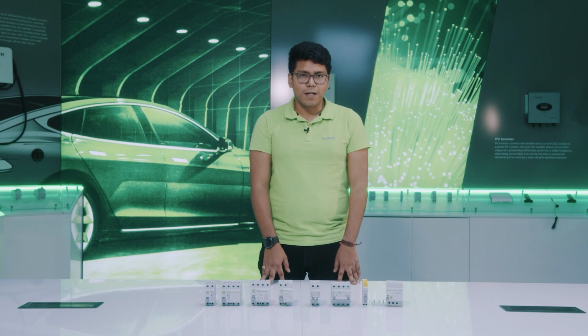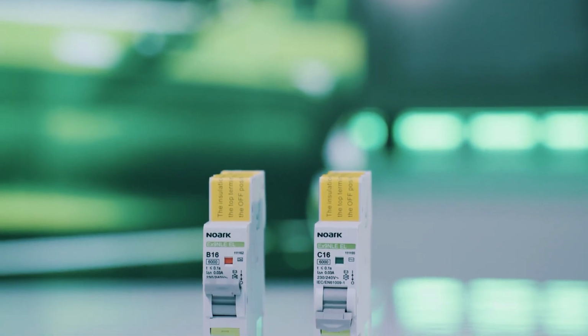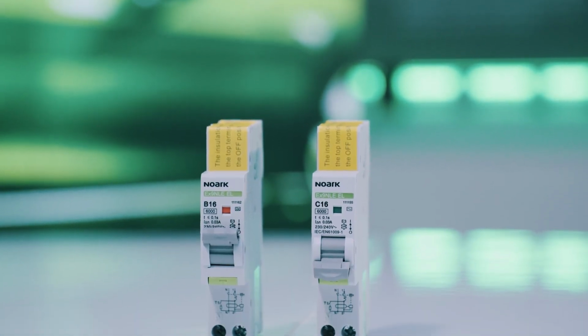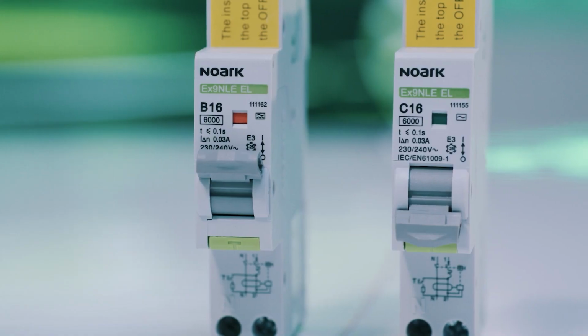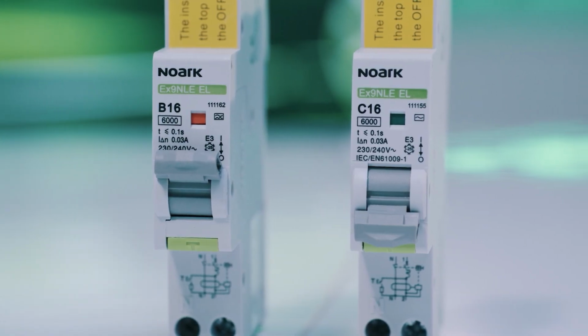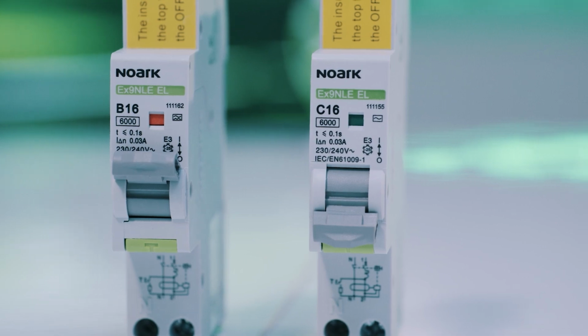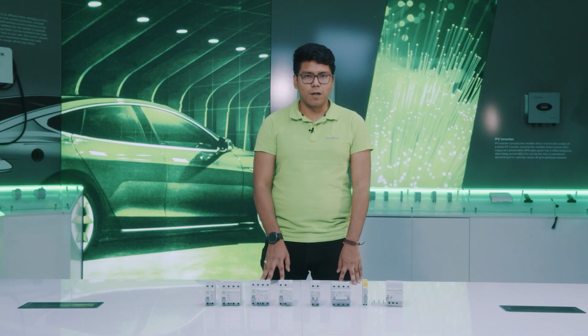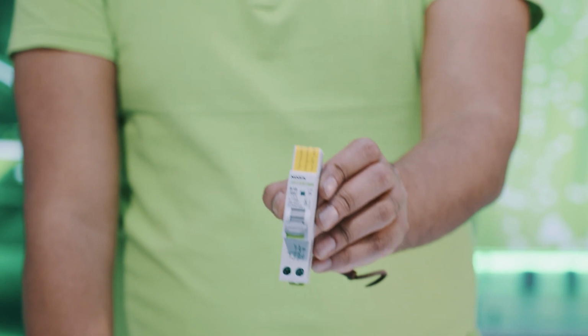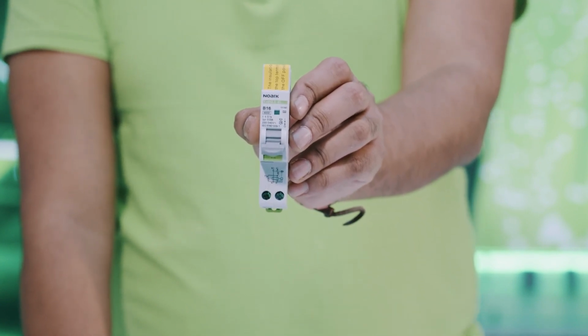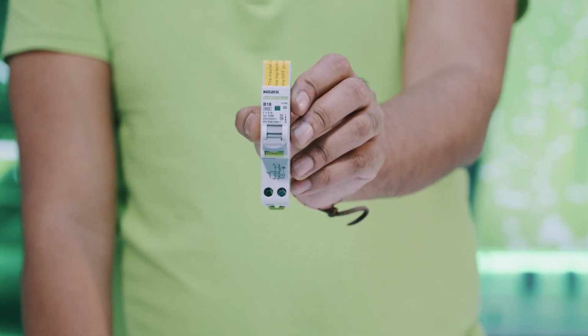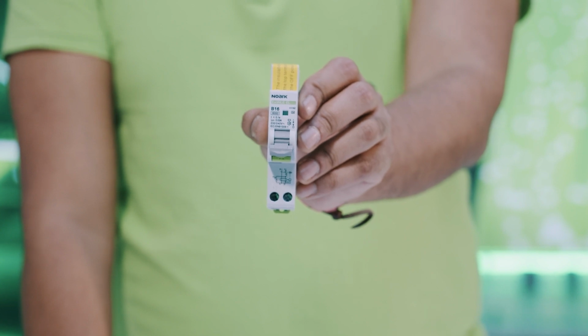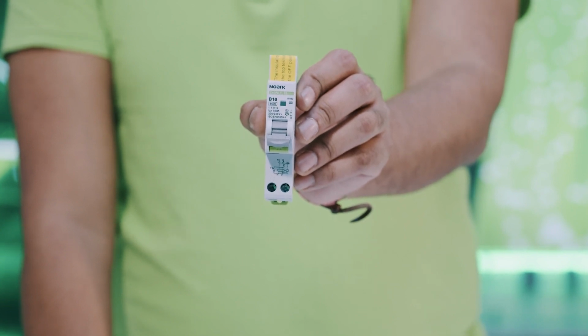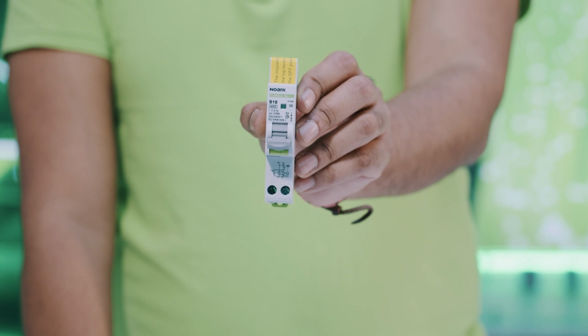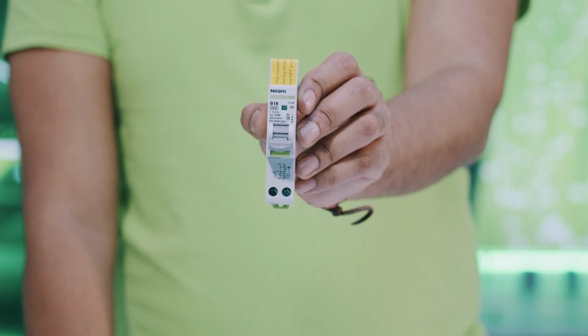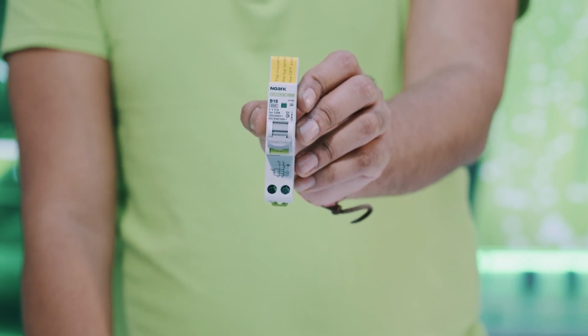Another type is the EX9NLE. These RCBOs have only one module width, so they can save one modular space in the enclosure in comparison to a classical RCBO. They are based on the electronic evaluation principle, with more accurate measuring of residual current. These devices also do not suffer from magnetization of the tripping unit. They are provided in 2 pole version with 6 kA breaking capacities. Nominal current is up to 40 amps with AC or A type of RCCB and B or C characteristics of MCB. The residual current sensitivity is 30 milliamps.